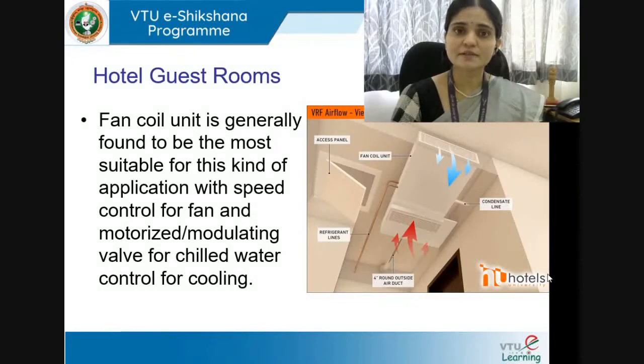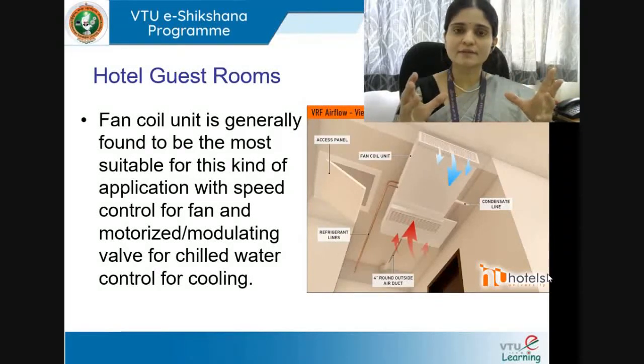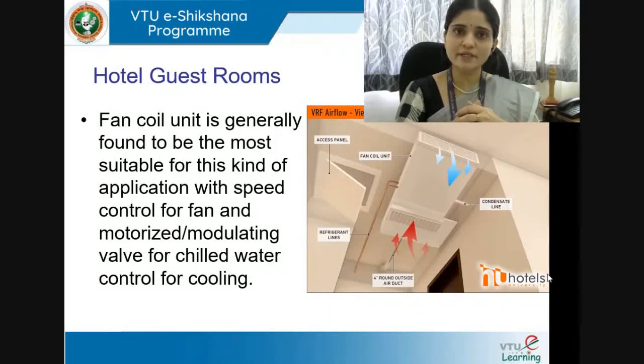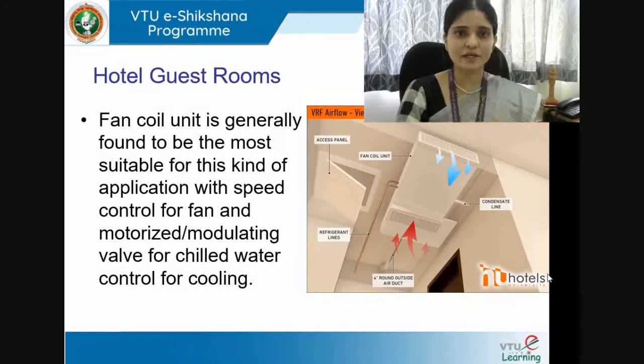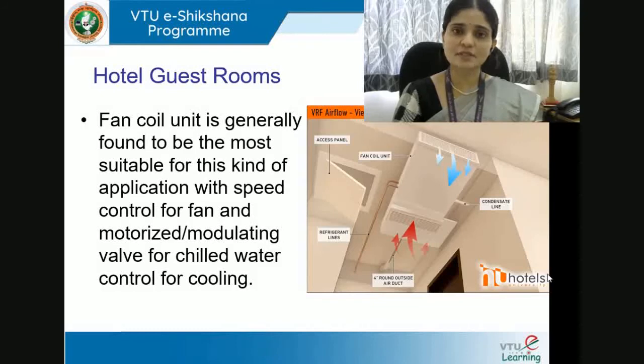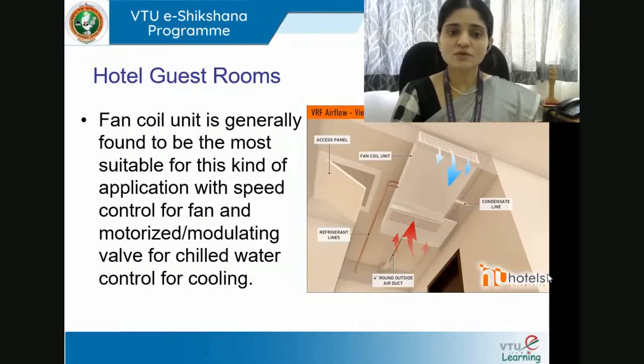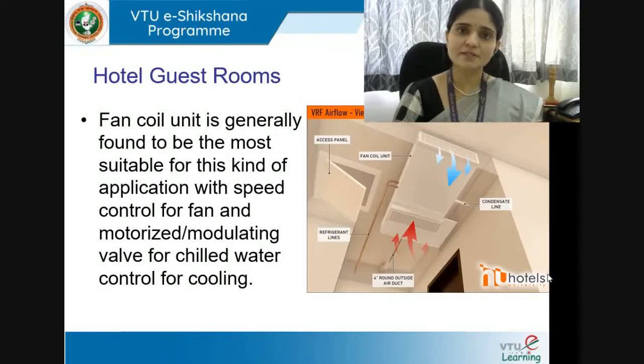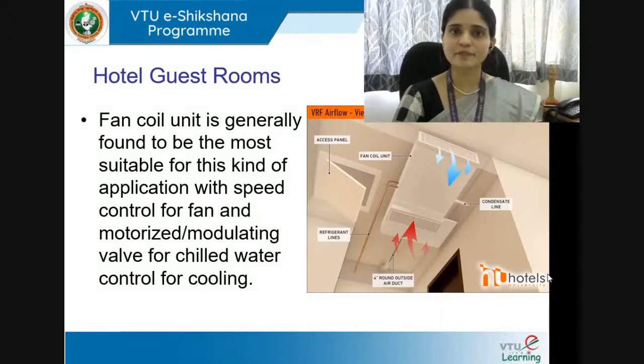The fan coil unit is a small cabinet-enclosed, factory-assembled unit which has the evaporator coil, filters, fan, and motor embedded. It is the smallest version of the air handling unit and is generally found to be the most suitable for hotel guest room applications. It typically includes speed control for the fan and a motorized modulating valve for chilled water control. The condenser-compressor is a single plant from which many evaporators branch out.